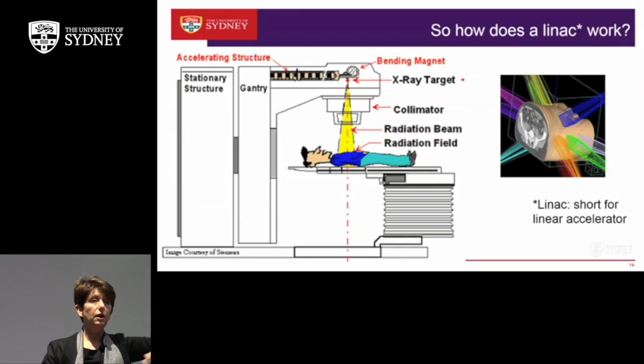So this is a schematic of what a LINAC looks like then. So here's a patient lying on a couch. This is called a waveguide. Electrons accelerate down a waveguide. The electrons, of course, have got a charge. So in a magnetic field, we can rotate them through 90 degrees. We send them through, they strike a target. So the electrons strike a target to produce the X-rays, and they then pass through a collimator, and that shapes the field. So it matches the shape of the tumour. And so the tumour, of course, is sitting deep inside the patient. What we do is we actually shoot the radiation from lots of different areas. So we're shooting the radiation beams, so they're focusing on the target. So the thing to be aware of course, is the radiation has to pass through normal tissue and to hit the target. So by bringing it in lots of different directions, the healthy tissue around the tumour gets a little bit of radiation, but most of the radiation is focused on the tumour.